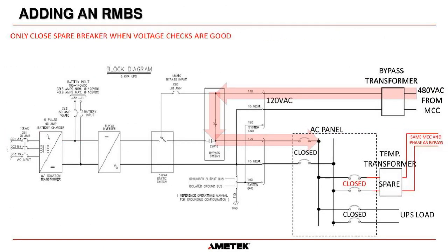Once we've done all the voltage checks and everything's good, we can now close this breaker and start to feed power back through this breaker out to the UPS loads here. At this point, the bypass transformer and the temporary transformer are going to be in parallel, and that's okay. There's no issue with that as long as we've done all of our checks.